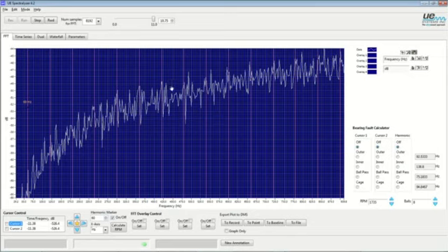When we refer to destructive corona, the easiest way to think of this is, we still have corona occurring, but it becomes destructive when it begins to track. So when the discharges of energy occur, it's related to nitrates and nitric acid that forms, and when that forms, it degrades the insulators and weakens them. And again, we get tracking occurring on those insulators. So in the time domain, I'm really looking for the same tracking spectrum.